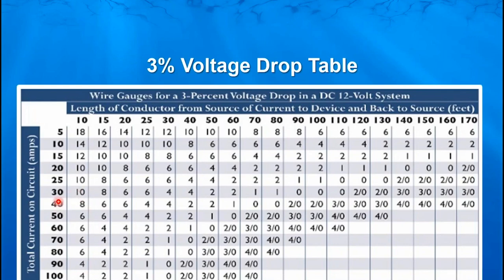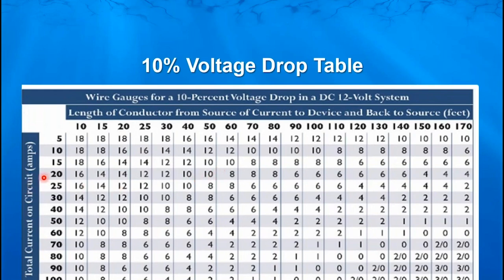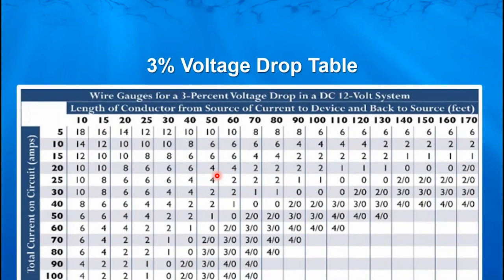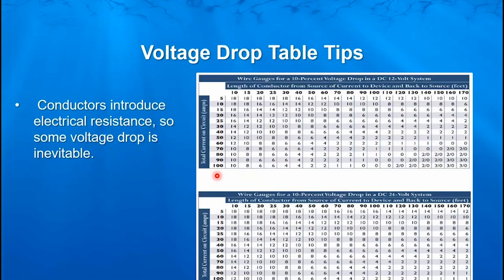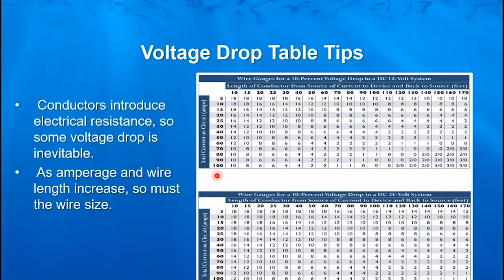On our 3% table, for 20 amps on a 50-foot circuit — that's 25 feet out and 25 feet back — we've got to use a piece of number 4 cable. That's a fairly substantial piece of cable. Compared to our 10% volt drop table, for 20 amps at 50 feet, we only need a piece of number 10. So there is quite a sizable difference in wiring between 3% and 10%. Conductors introduce electrical resistance and some voltage drop is inevitable — we can't have zero voltage drop, but 3% is pretty close. The general rule is: as amperage and wire length increase, so must the wire size.